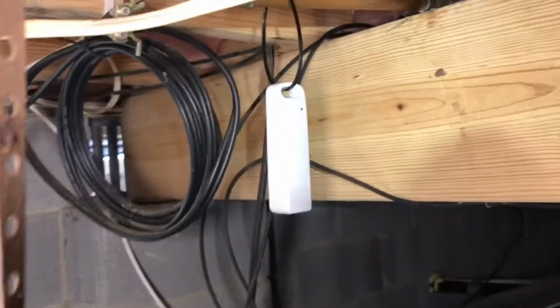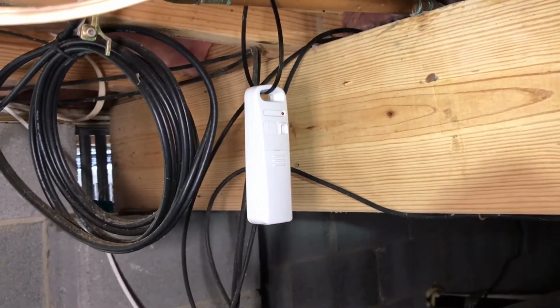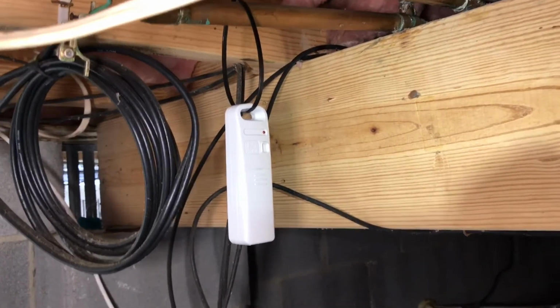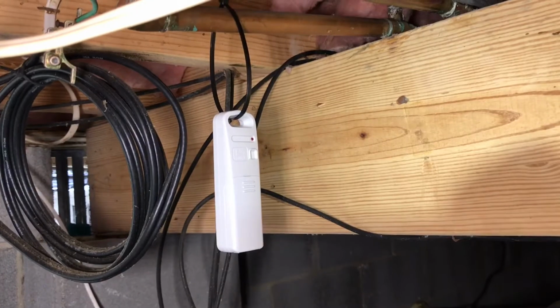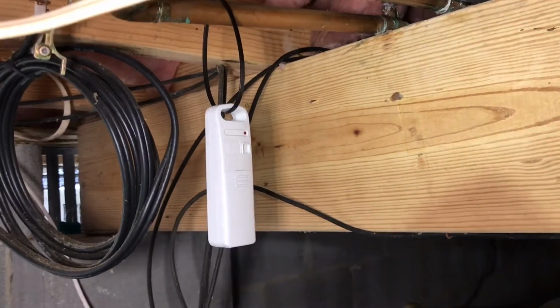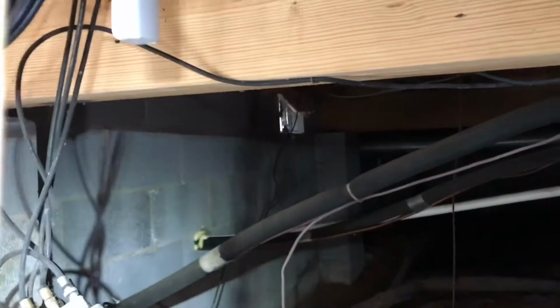Also, another thing we did is I loaned them a relative humidity and temperature wireless monitor made by AcuRite. Pretty low cost, I think they cost about $15, but we're actually measuring 89% humidity in here right now, and it's February, so it's going to get worse. And we know that above 70%, bad things happen.